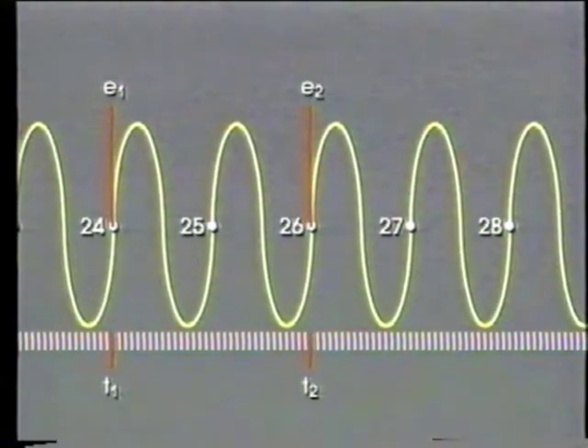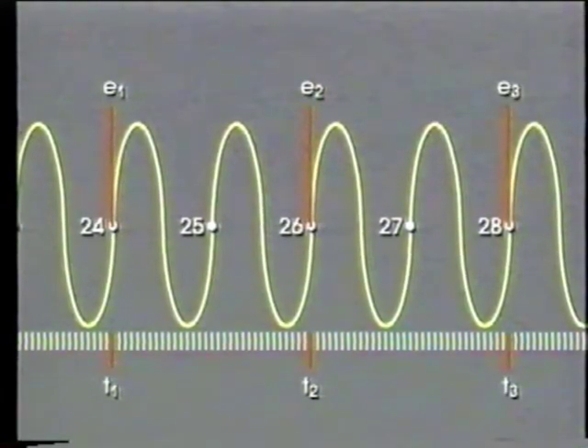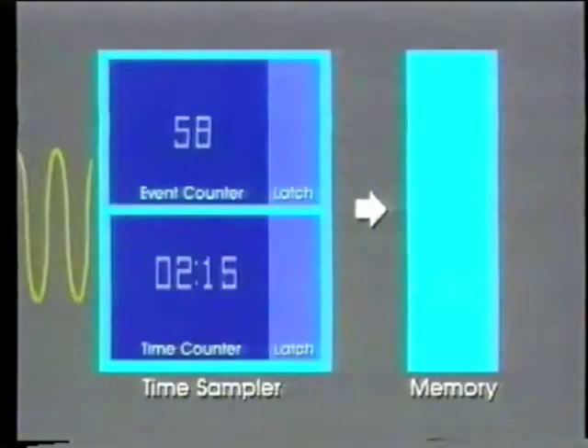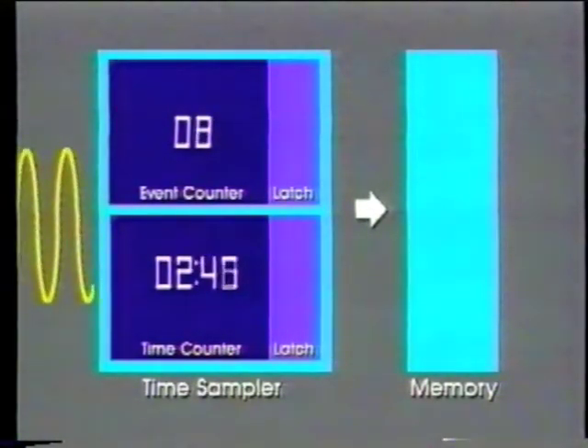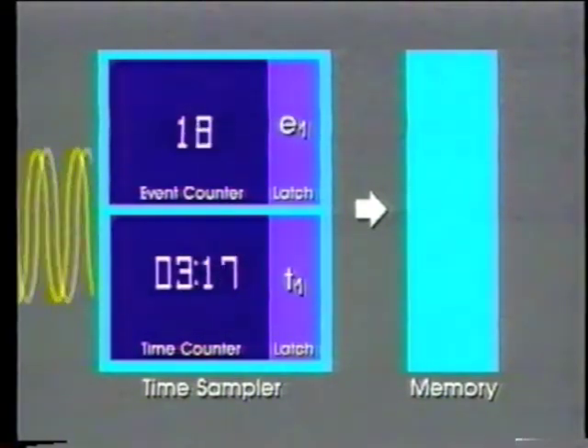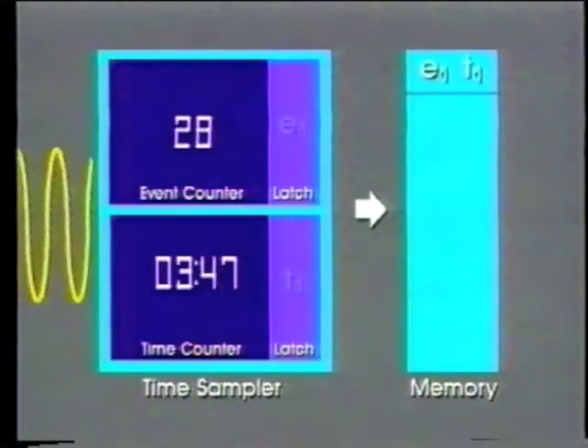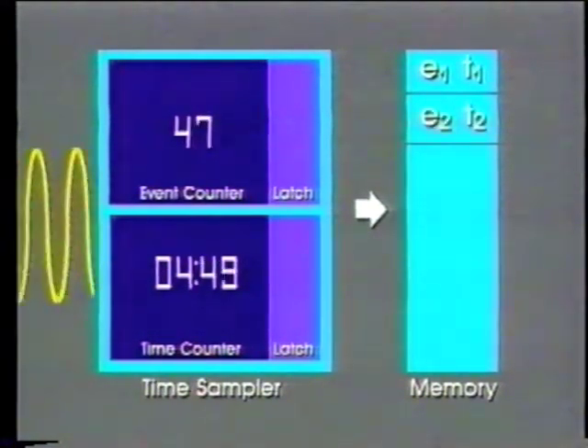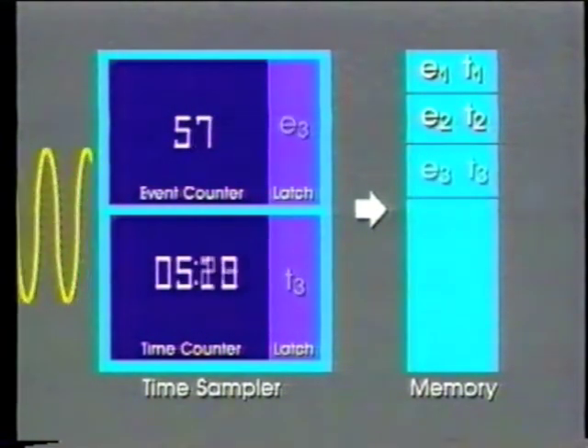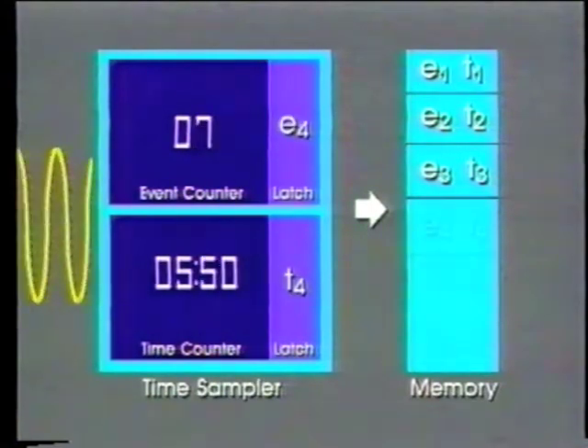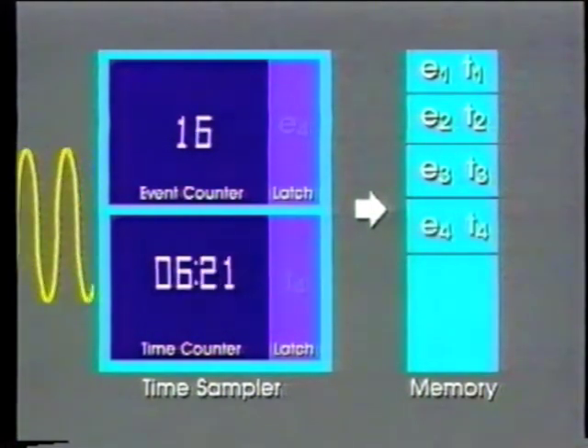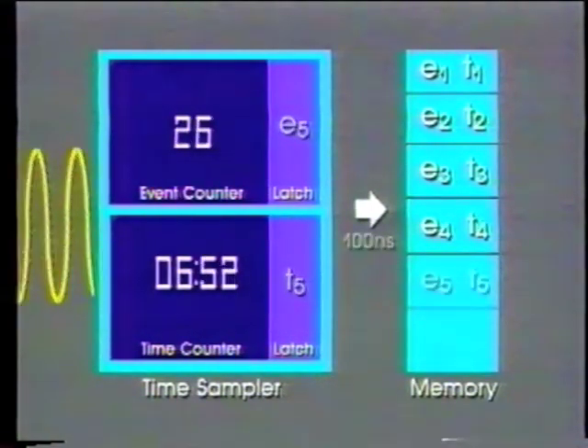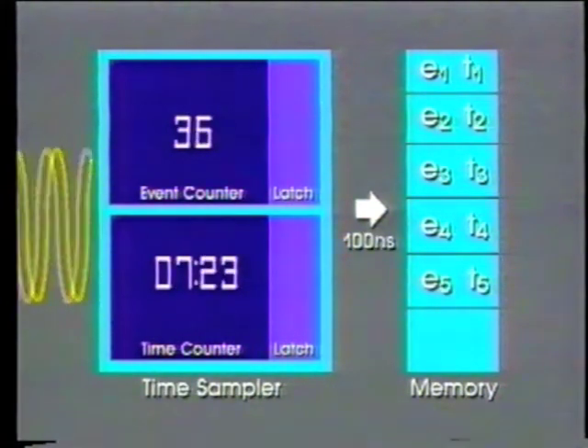Unlike traditional frequency counters, the 5371A does not stop between measurements to store and process the data. Instead, it continues counting new events and times while it is storing those already latched. That means there is no dead time between measurements, so no information is lost. With this continuous count feature, data can be latched very quickly and stored in memory as fast as every 100 nanoseconds.